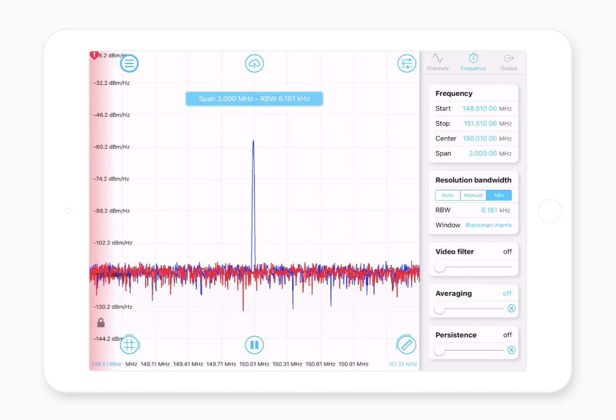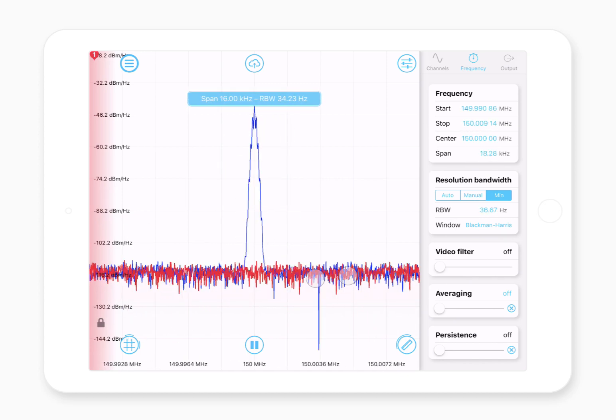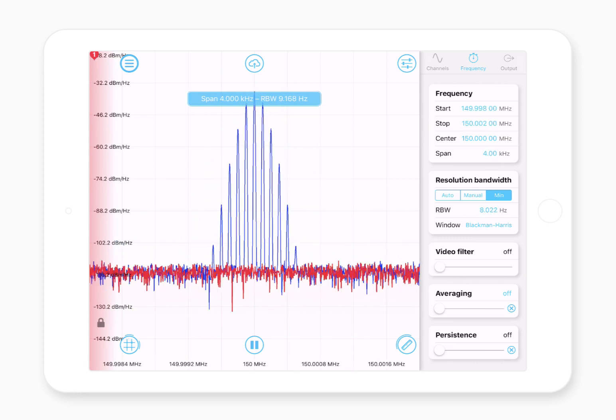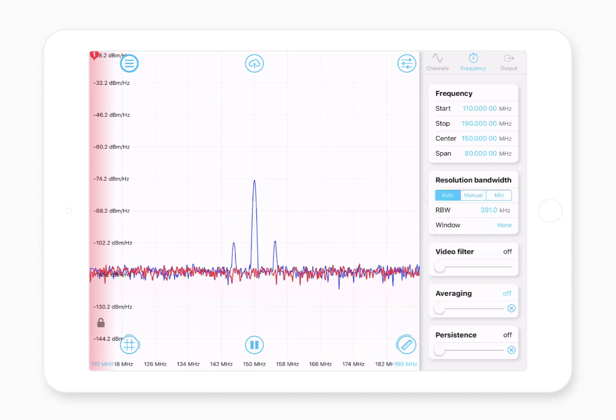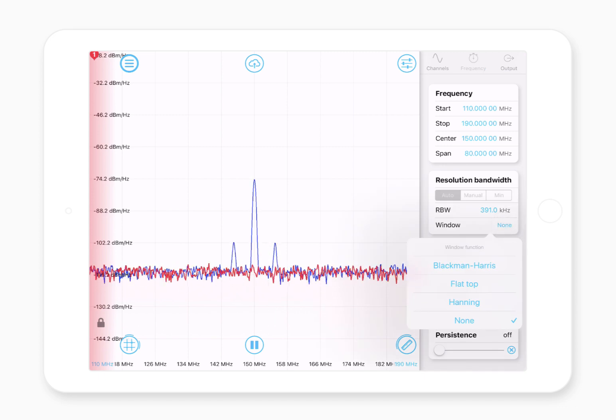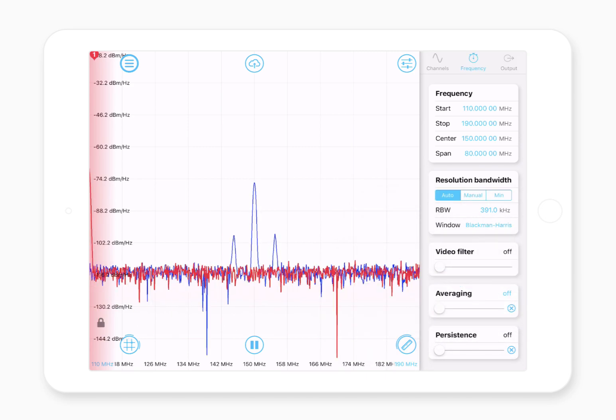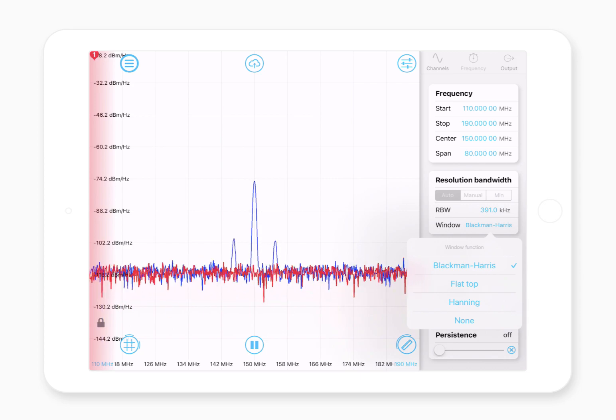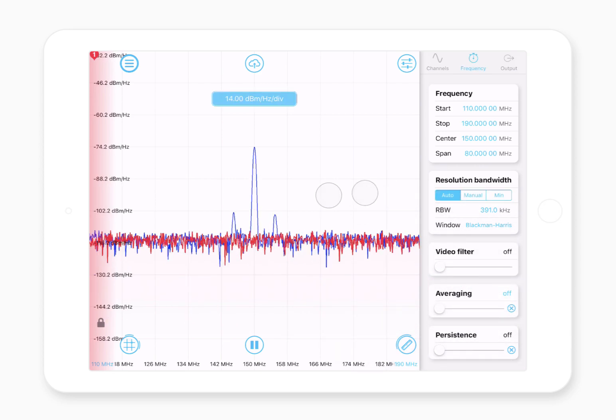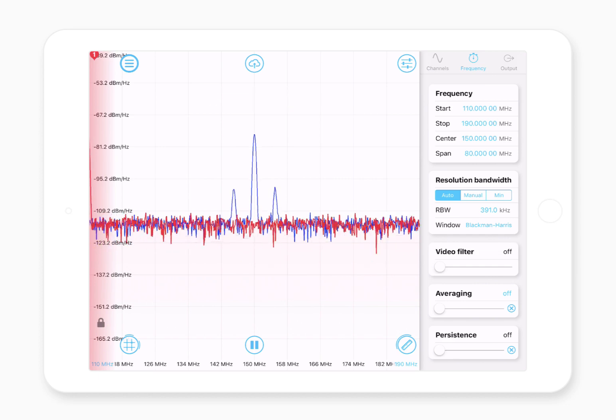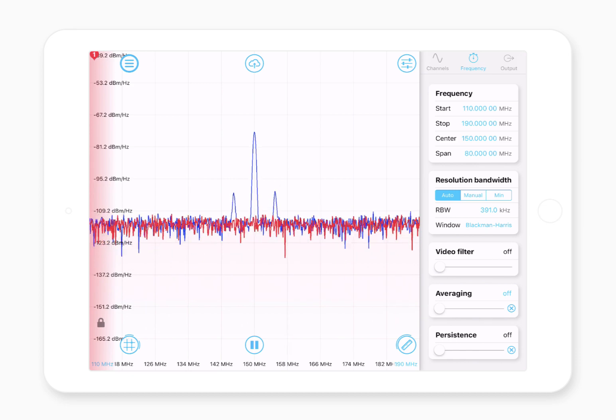Zooming all the way out revealed something interesting — that central peak at 150 MHz actually has some structure to it, which is a nice little surprise. The other thing you can do is change the windowing. You can select from four options: no windowing, which can give quite a lot of spectral leakage; Hann window; Blackman-Harris; and flat top. Most of the time Blackman-Harris is a pretty versatile window. This is important for making sure that what you're seeing in the spectrum is actually signal and not just an artifact from the hybrid super-heterodyne FFT algorithm that the instrument uses.